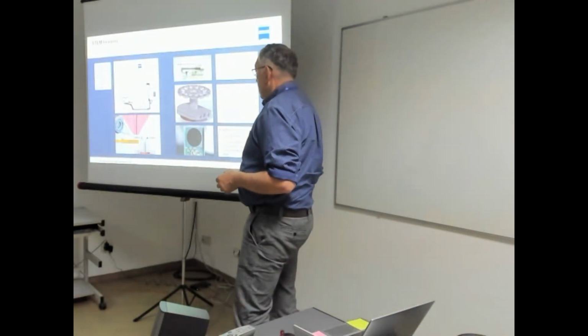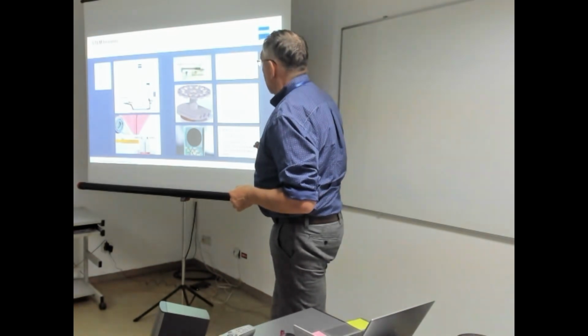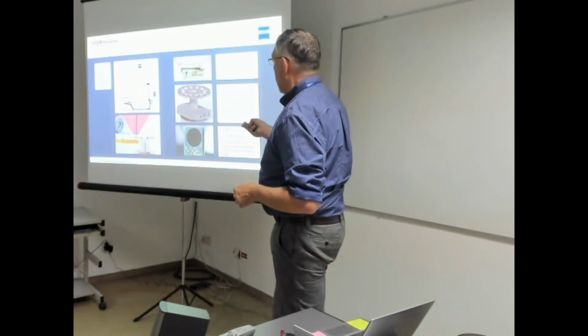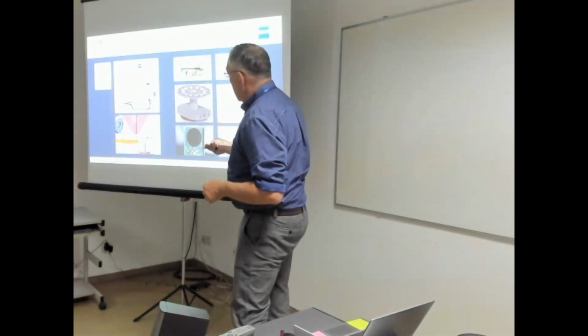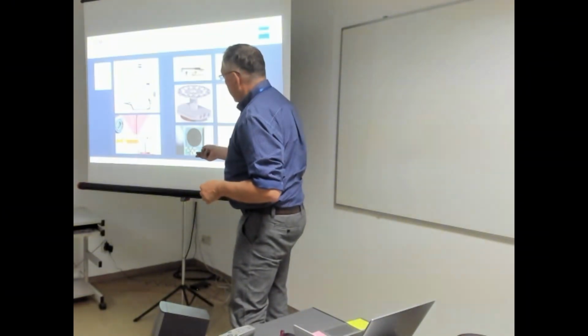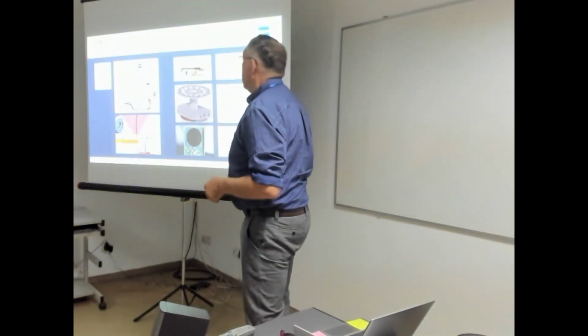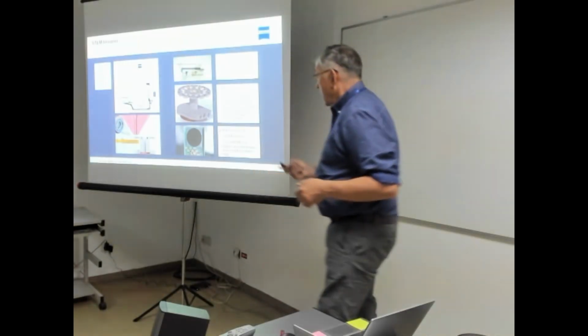If you look at this, how does it look in our days? We have these typical small grids with our samples on it. We have carriers like this 12 revolver carrier here. This goes into an SEM.